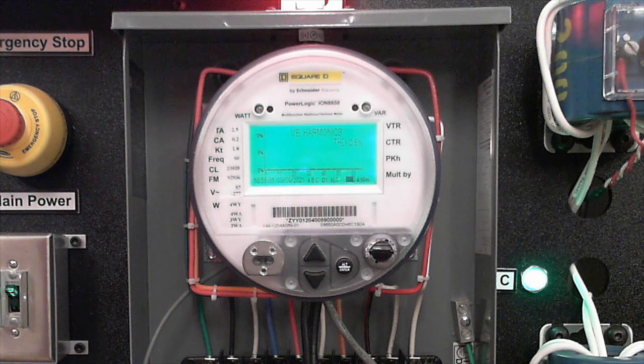One more quick question. MBDA asks, power quality monitors have to be calibrated yearly. How does this apply to the Schneider meters? That would be the same. Any device that you're using for billing or regulatory, I believe requires annual testing. So having a test kit that can inject harmonics and then being able to see its impact can be critical when you're testing these types of devices.